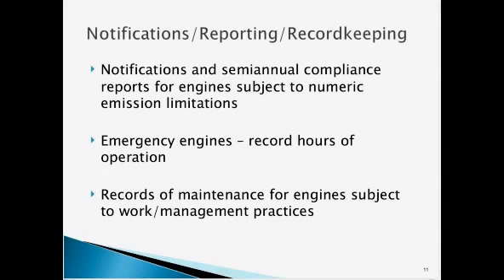In terms of the notifications and the record keeping and reporting that's required, those engines that are subject to a numeric CO limit or a percent reduction requirement have to submit the traditional notifications, such as an initial notification and notification of performance test. And they also have to submit semi-annual compliance reports. If you're an emergency engine, you don't have to submit any notifications, but you do have to record hours of operation. And then those engines that are subject to the work and management practices, the ones that don't have a numeric CO limit, they have to keep records of the maintenance conducted on the engine.